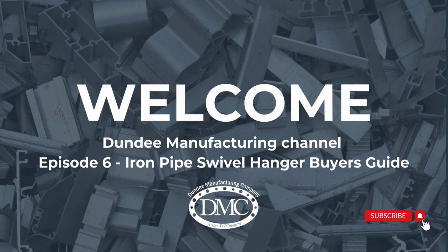Which brings up a critical tension in this entire system. We've established that we are introducing vertical movement via the swivel, and we might be using reduced diameter rods, but we're still suspending thousands of pounds of moving fluid over people's heads. So how do we ensure this flexible swivel point doesn't become the weakest link and just snap? The material science has to be absolutely bulletproof, right? Oh, absolutely. The material specifications in the 2026 guide reflect that exact engineering challenge. You cannot sacrifice ultimate tensile strength for the sake of job site convenience.